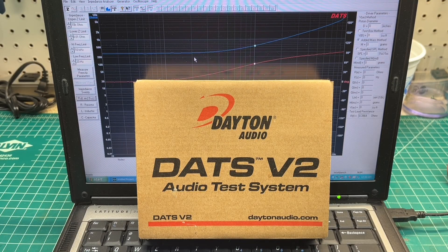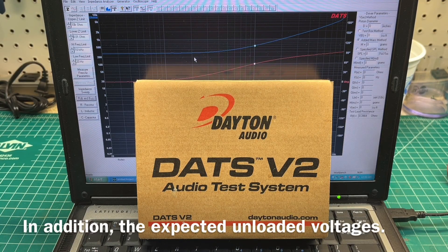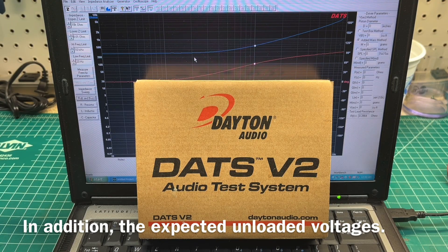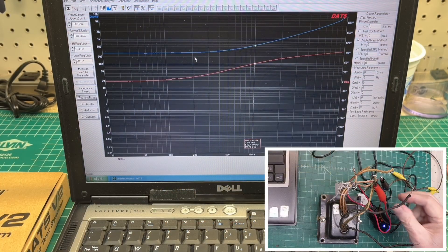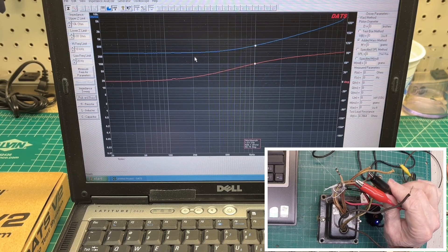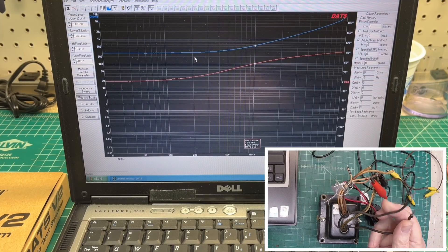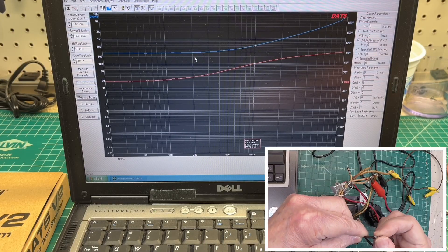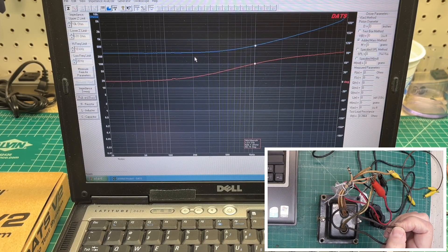So one use of the DATS version 2 — it's kind of interesting. I'm going to take a power transformer and somewhat reverse engineer it. I'm going to extrapolate what the high voltage number of turns would be, in addition to the primary turns and the secondary turns, also for the 6.3 and 5 volt winding, just using the DATS system and some simple math. First thing I want to do is hook up the test leads for the DATS unit across the entire secondary high voltage winding — you can see them attached here — and I'm going to short out the primary winding. What we can do is determine what the leakage impedance is of the transformer.